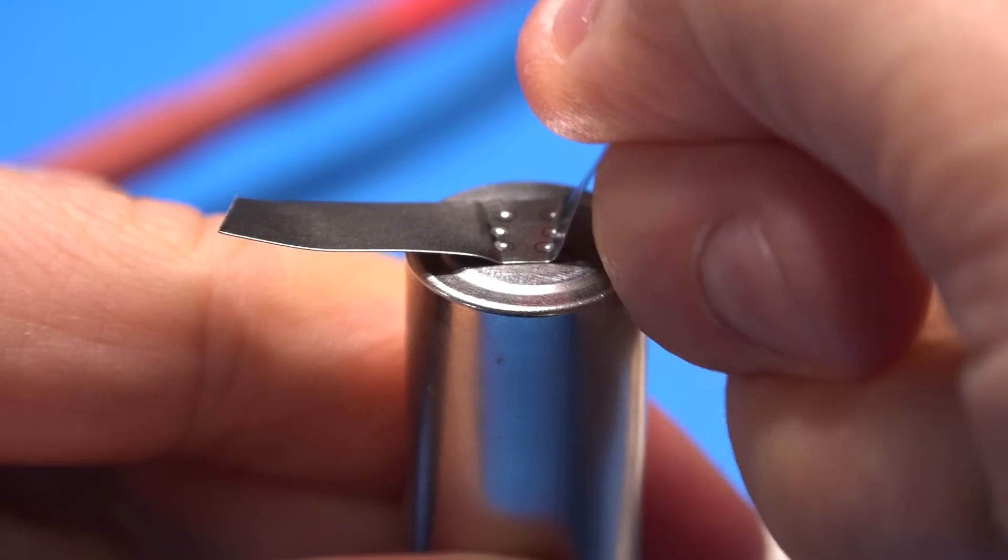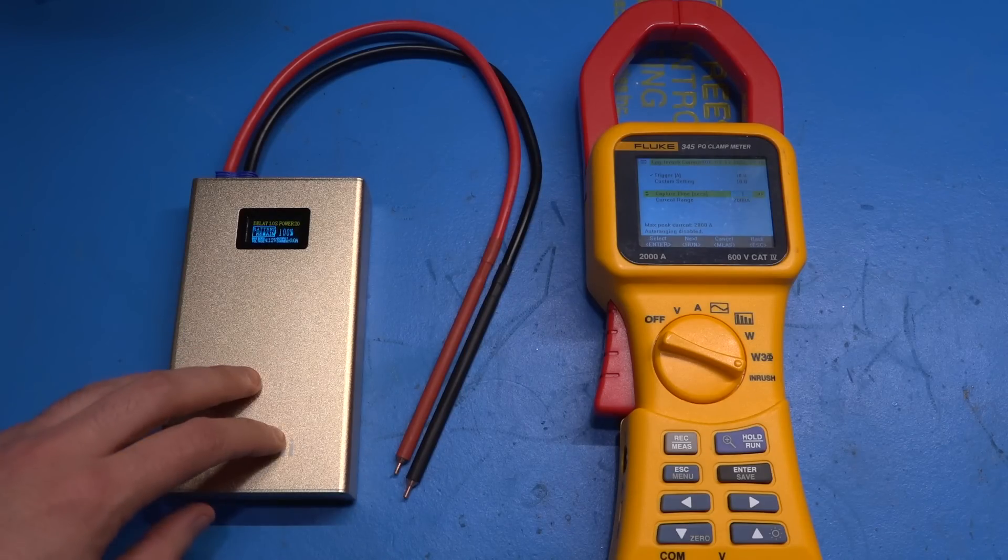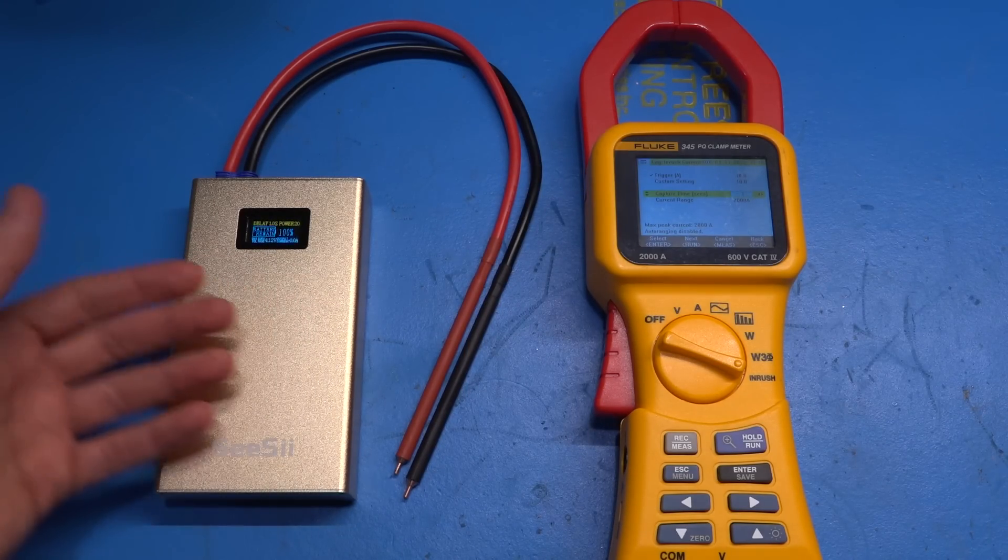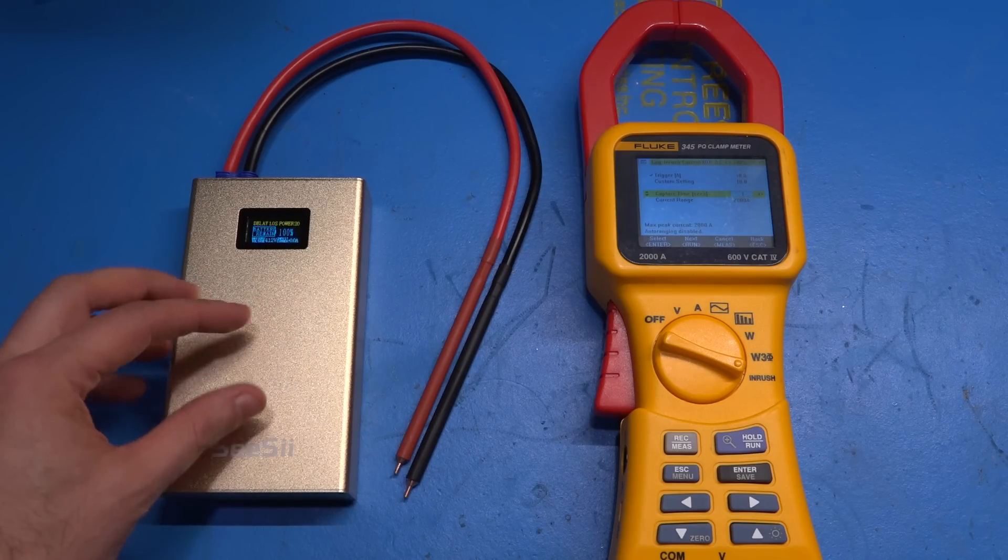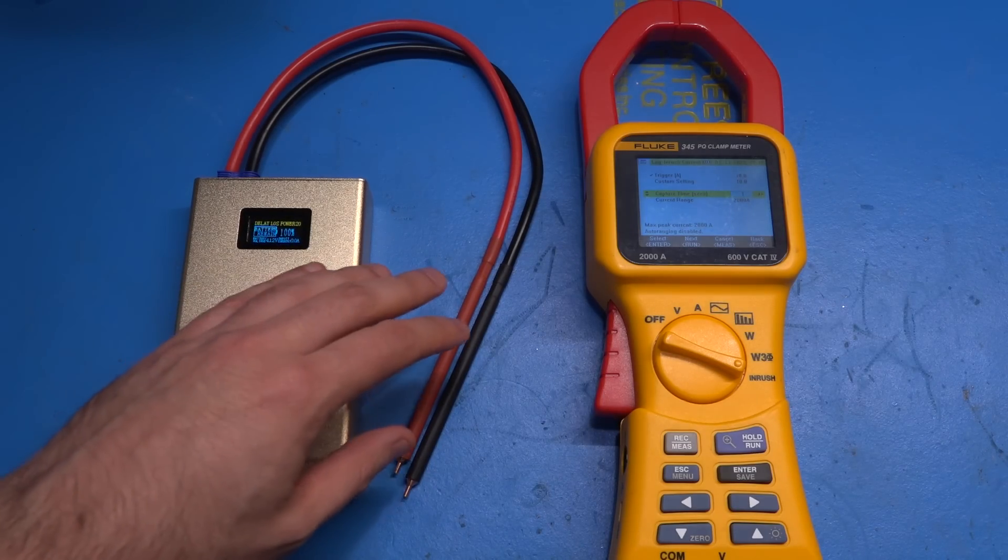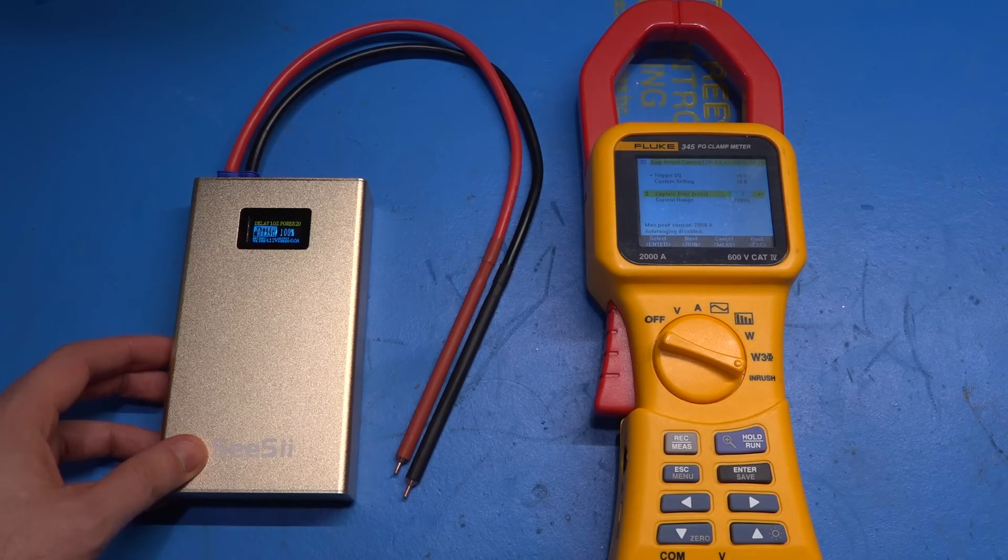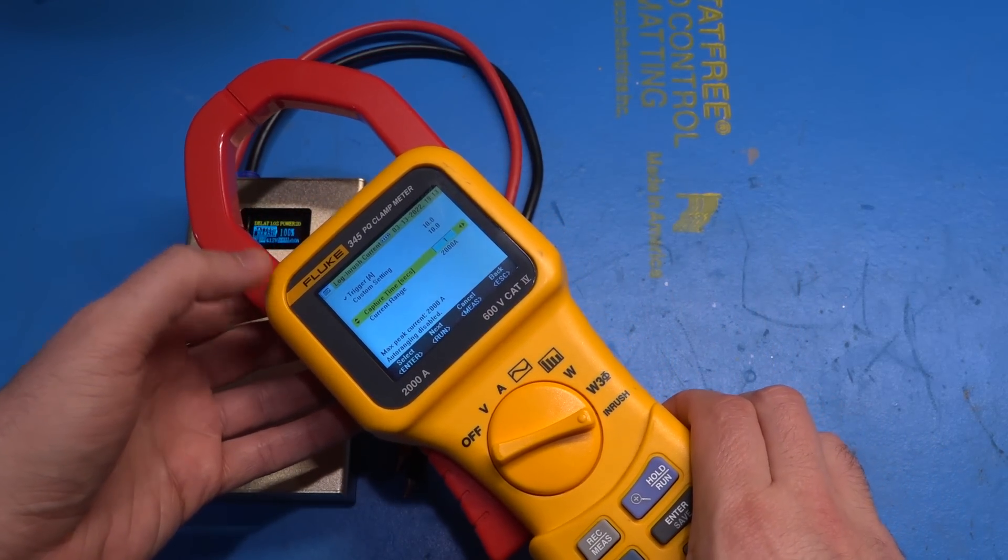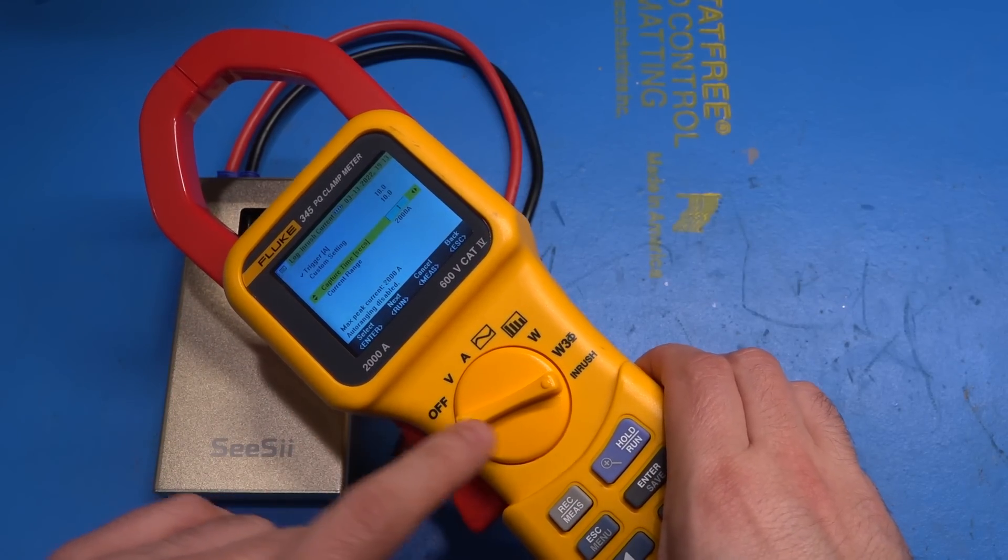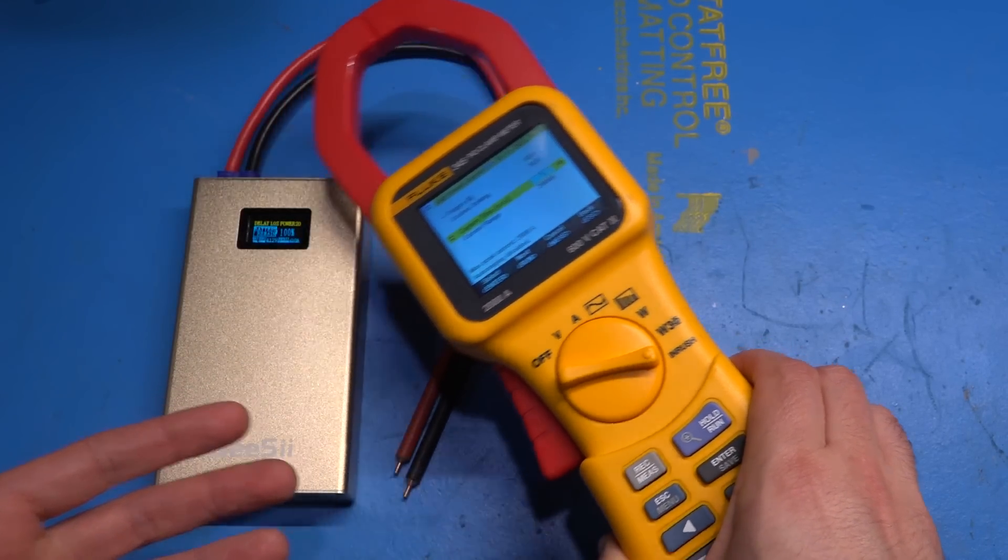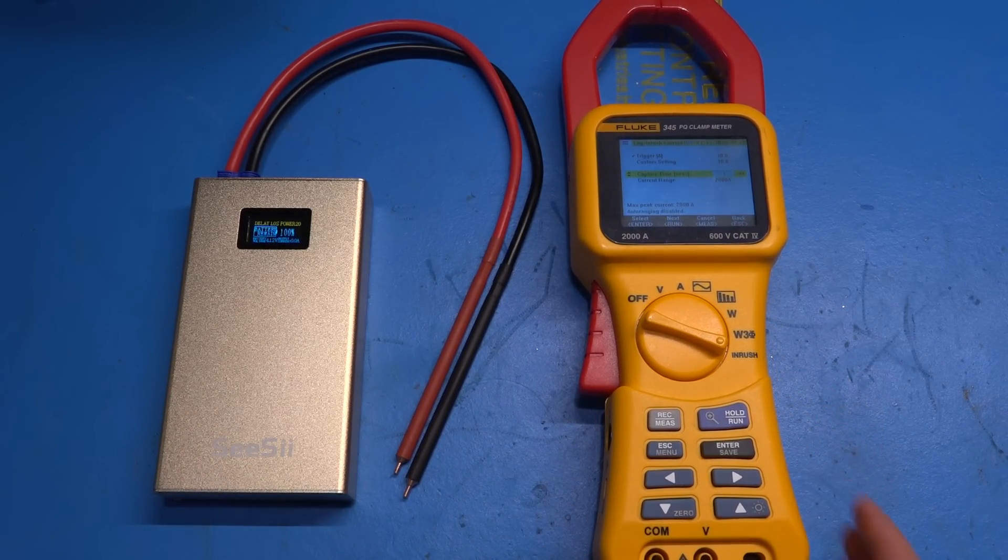All right, let's measure the maximum current. Now to measure the maximum pulse of current that comes from something like this can be somewhat challenging, because the current could be more than a thousand amps and the pulses are fairly narrow. So you have to capture it somehow. If you don't have the appropriate current probe you may not be able to do it. But of course here we have the Fluke 345 PQ clamp meter, which I repaired in one of the previous videos, and this thing goes up to 2000 amps. It has an inrush function where it can trigger itself, arm itself, and then measure a small pulse of current going in.